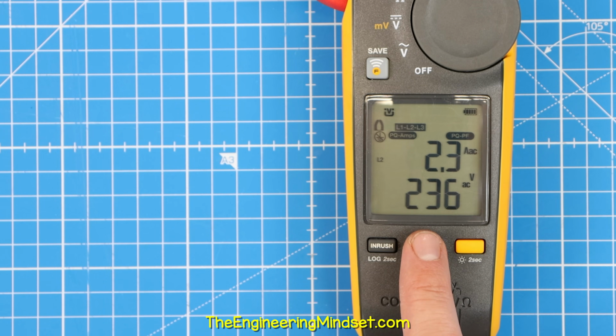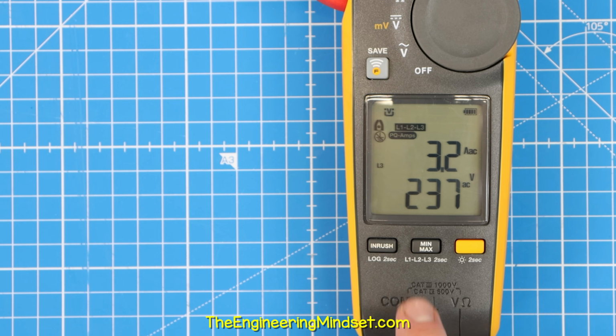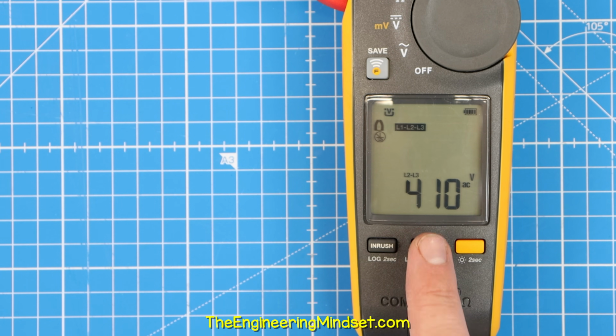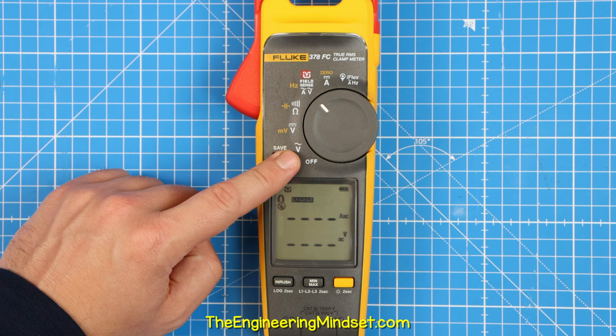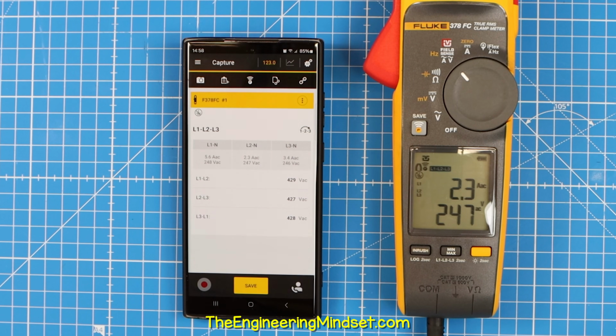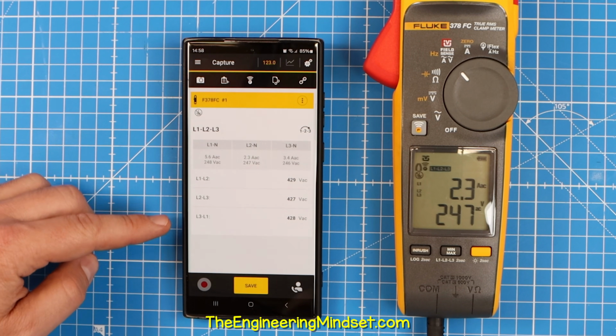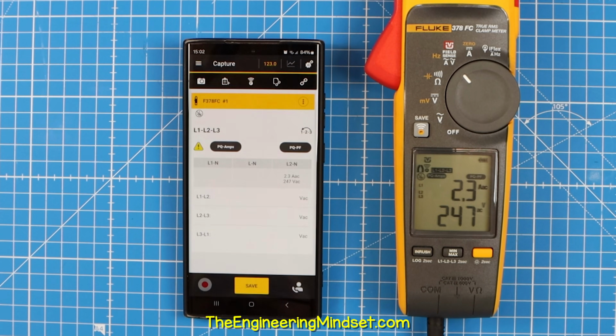It then tells us the line to neutral voltage and line current, and it then tells us the line to line voltage. If we use the Fluke Connect app, it also tells us the phase rotation to ensure the correct order of installation. This one can also tell us about power quality issues if it detects them.